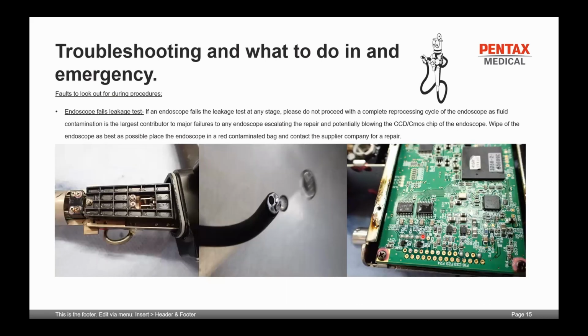Okay. If an endoscope fails a leakage test at any stage, please request either the cleaning or the CSSD staff not to proceed with a complete reprocessing cycle of the endoscope, as fluid contamination is the largest contributor to major failures of any endoscope, escalating a repair to potentially blowing a CCD or CMOS chip of the endoscope.